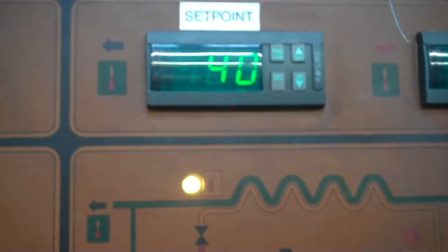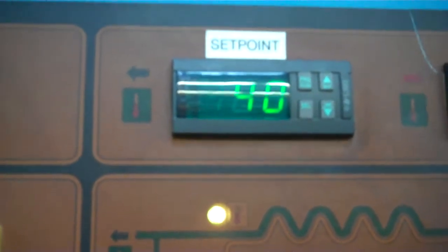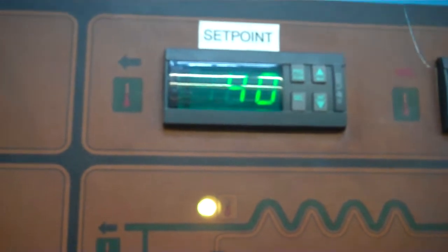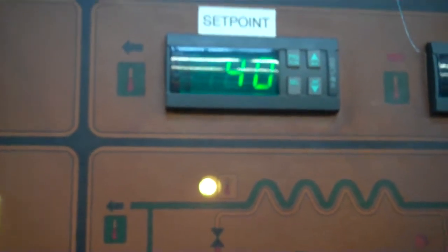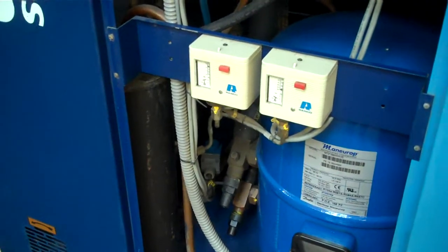So you probably heard the compressor stop. It's normal. We'll have some residual cooling. We'll go a little bit below that 42 degrees, maybe by 3 or 4 degrees for a second. The fans turn off, and the pump will continue running all the time.